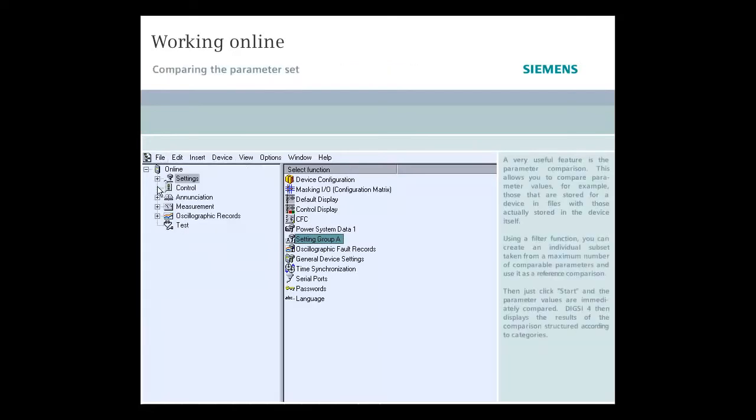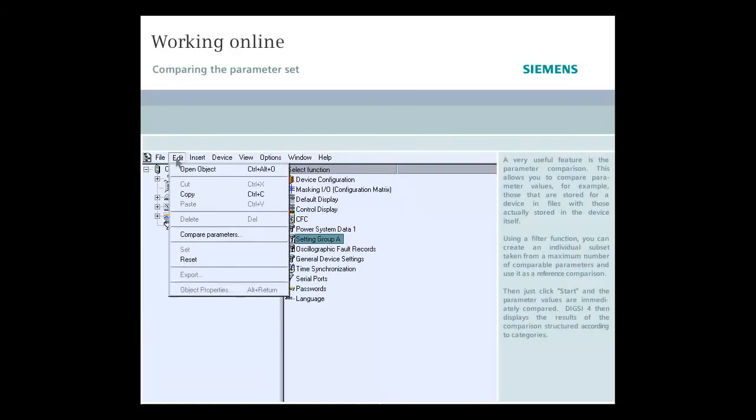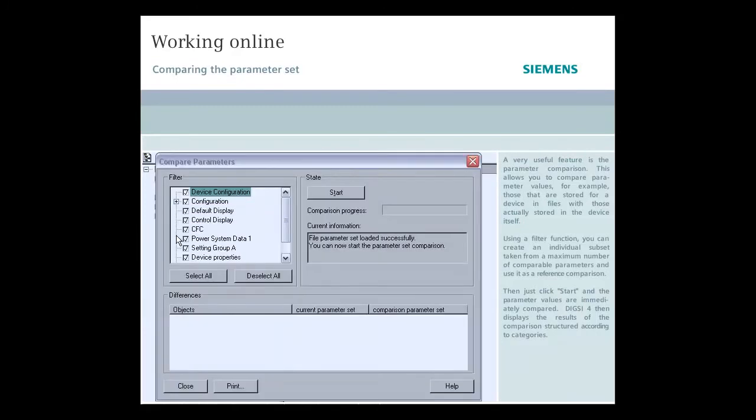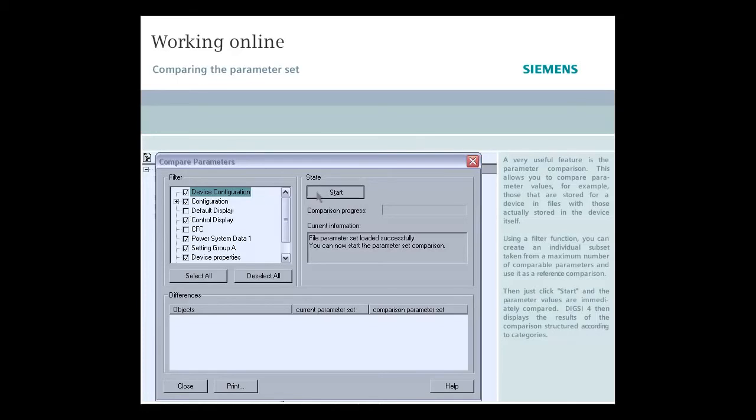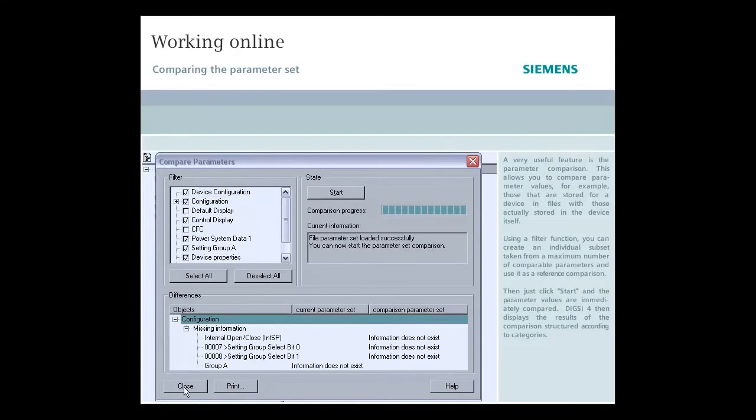A very useful feature is the parameter comparison. This allows you to compare parameter values, for example, those that are stored for a device in files, with those actually stored in the device itself. Using a filter function, you can create an individual subset taken from a maximum number of comparable parameters and use it as reference comparison. Then just click Start, and the parameter values are immediately compared. DIGSI 4 then displays the results of the comparison structured according to categories.